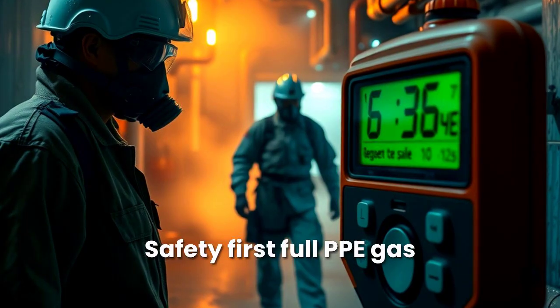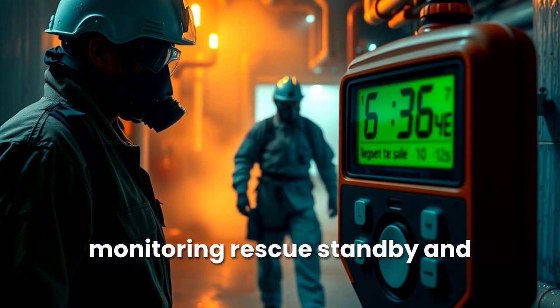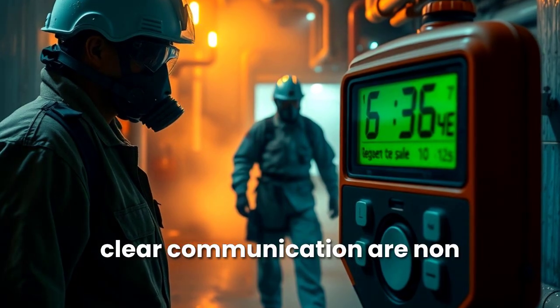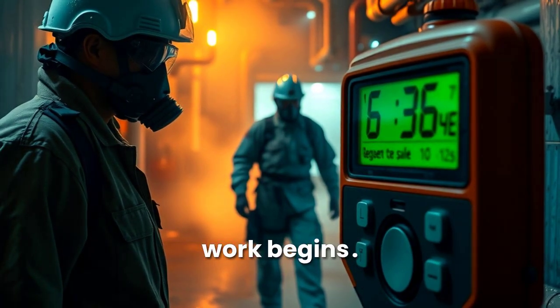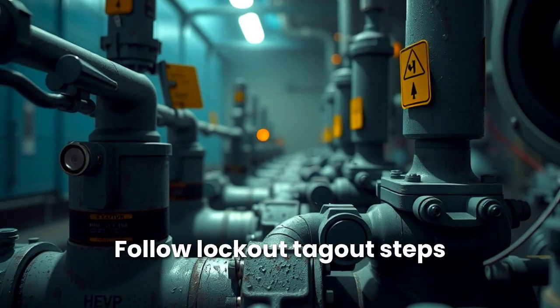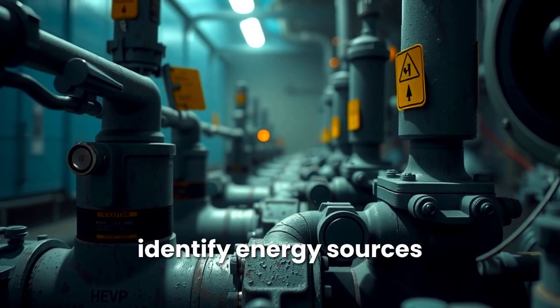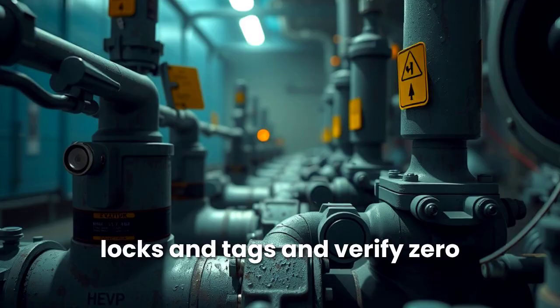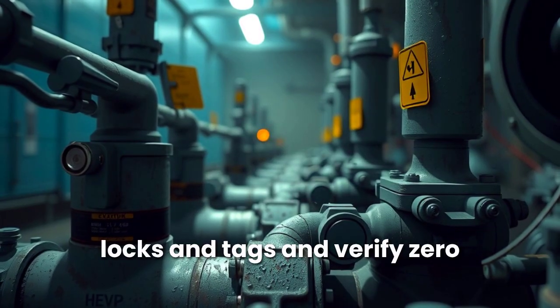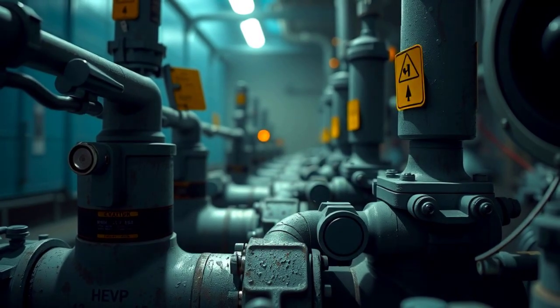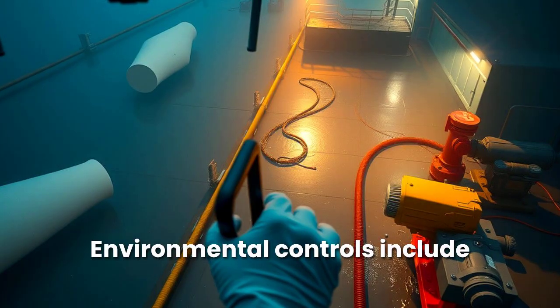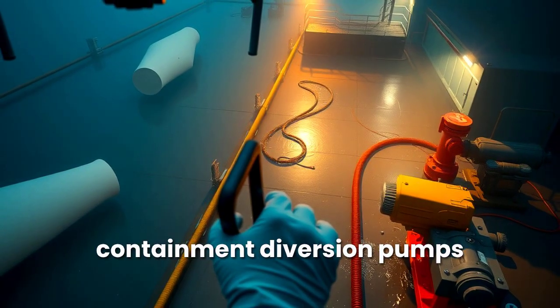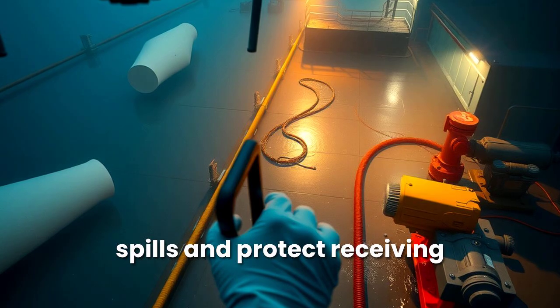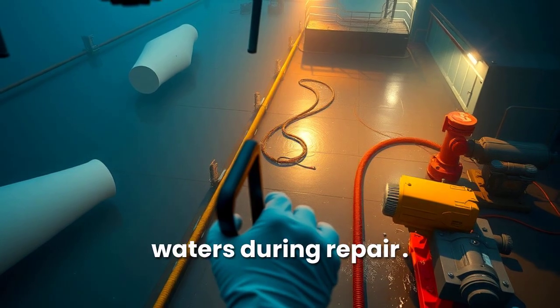Safety first: full PPE, gas monitoring, rescue standby, and clear communication are non-negotiable before any valve work begins. Follow lockout, tag out steps: identify energy sources, isolate bleed lines, apply locks and tags, and verify zero energy state before entry. Environmental controls include deploying temporary containment, diversion pumps, and absorbents to prevent spills and protect receiving waters during repair.